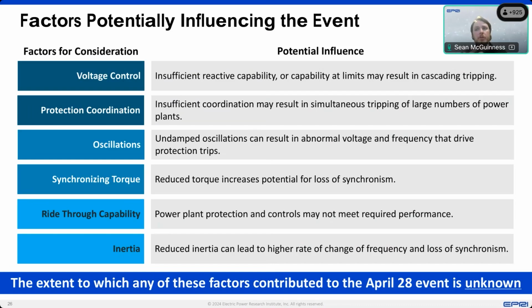This isn't to say that every power plant should have a different voltage set point, but it is recognizing it as a potential common mode failure. If a part of a grid does experience a high or low voltage, how exposed are the power plants in the area to potentially all tripping near simultaneously in response to that? So as I say, it's power plant coordination, and also recognizing that this has to be coordinated with each other.